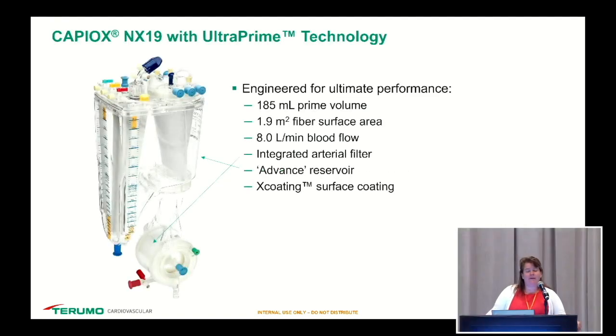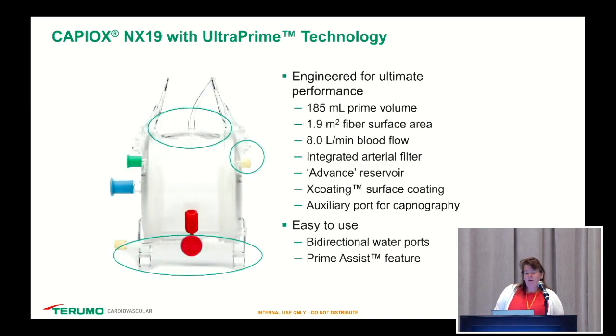So as the video had alluded to, the CAPIOX NX19 with UltraPrime technology is engineered for ultimate performance. So it's 185 ml prime volume with a 1.9 fiber surface area, with the integrated arterial filter, advanced reservoir as similar to the FX15 and 25, and the X-coating surface. It has that 185 ml prime volume, the 1.9 surface area. It is 8 liters of blood flow, which is our highest rated flow oxygenator in our market.